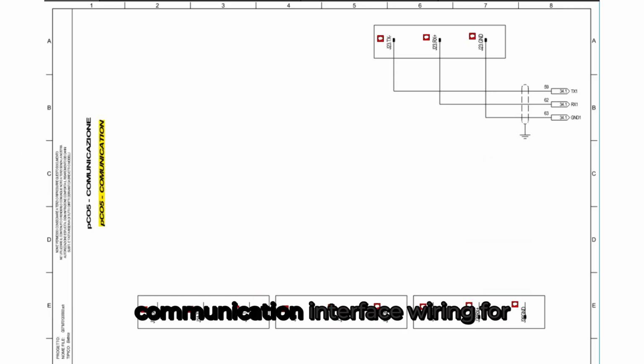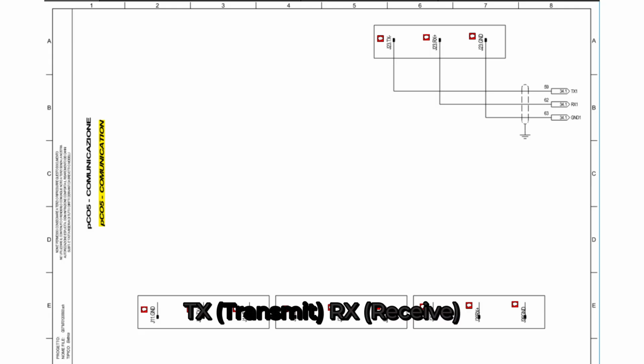This page shows the communication interface wiring for the Carel PCO5 controller. Here, we see a small communication block labeled J23, which includes 3 terminals: TX, transmit, RX, receive, and GND, signal ground. These are standard serial communication lines used for RS-485 communication. This is communication between the PCO5 and the expansion valve driver.